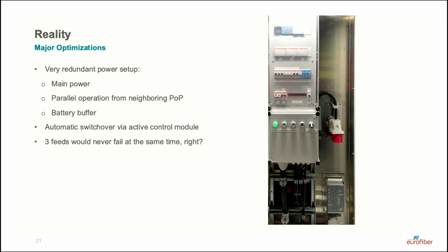One last thing that might be entertaining: we thought we had a very redundant power setup. Firstly, of course, we have the main commercial power coming in on one feed. But we also had a second feed coming in from the neighboring cabinet, since we always put those in pairs of 2 on each heat plant site for redundancy. So if our power would fail, the neighboring cabinet could still supply us, and if both should fail, we still have a battery buffer to run on for a couple of hours.